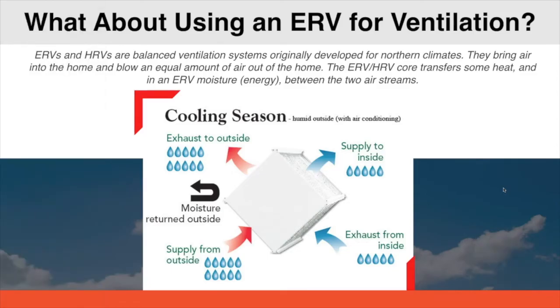So, ERVs. ERVs will always reduce the moisture load in the home, but it's never going to reduce it to a dedicated set point. So it's always going to lessen the load that you were bringing in from outdoor air, but it's always going to contribute continuously to the moisture load in the house. It's just not going to be bringing in as much as if you were just doing an exhaust or a supply strategy.